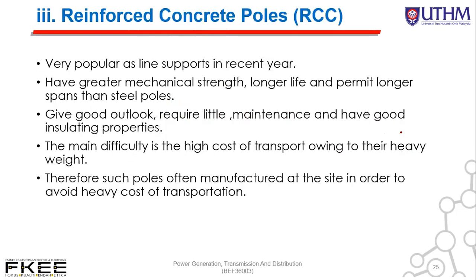Reinforced concrete poles are very popular as line supports in recent years. They have greater mechanical strength, longer life, and permit longer spans than steel poles. They give a good appearance, require little maintenance, and have good insulating properties. The main difficulty is the high cost of transport due to their heavy weight. Therefore, such poles are often manufactured at the site to avoid heavy transportation costs.